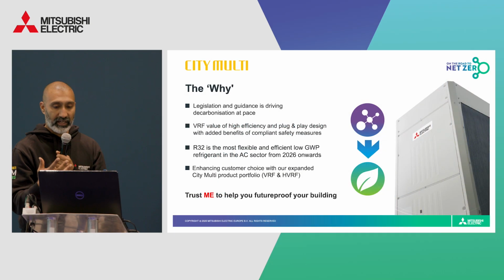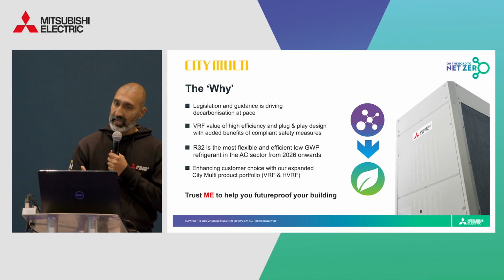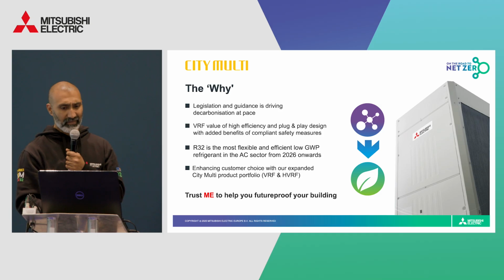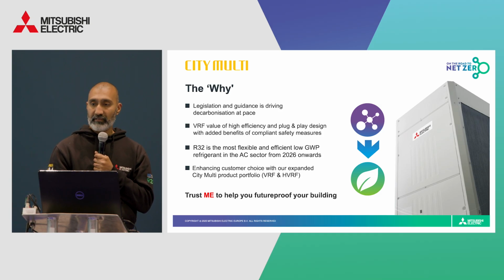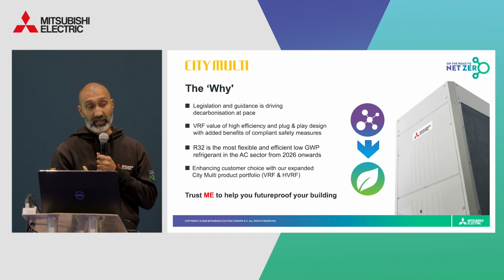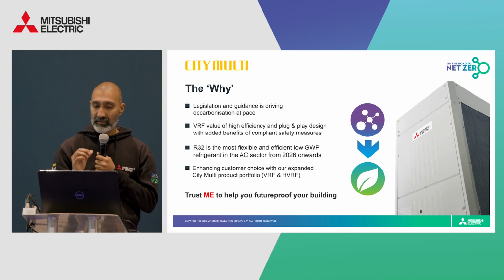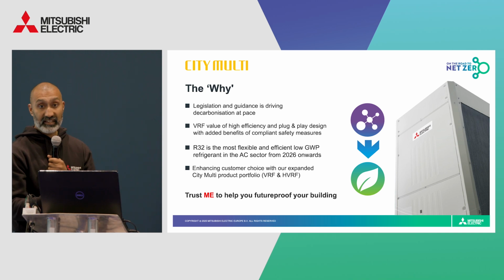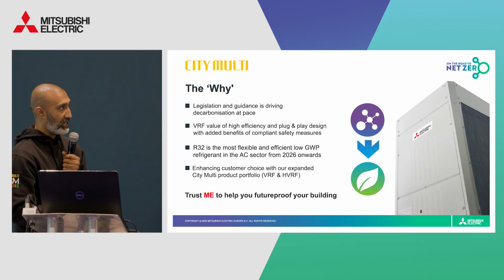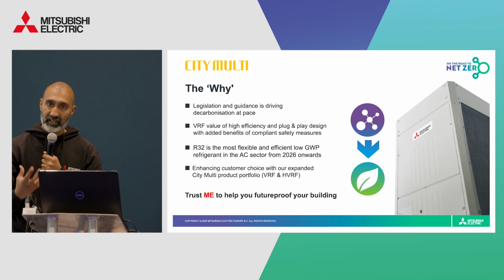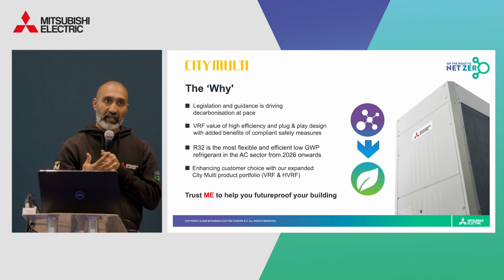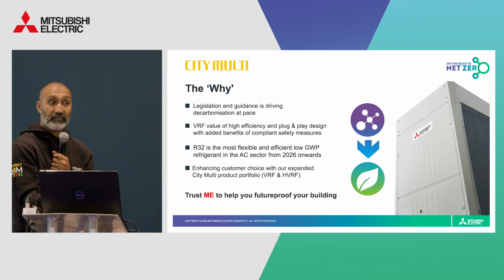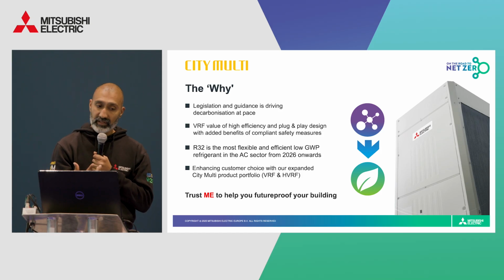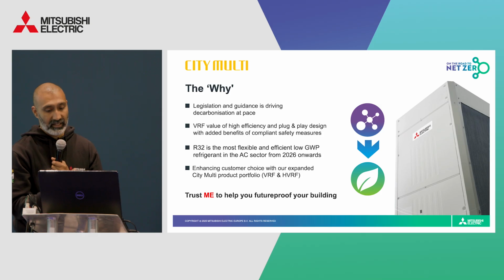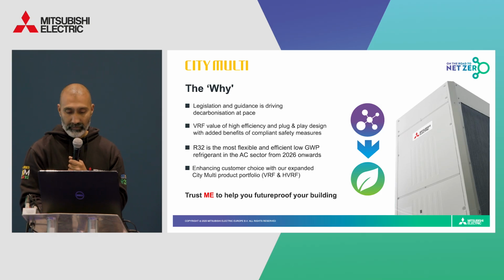Now, we mentioned this already a few times. The EU F-gas regulations will significantly impact the type of refrigerants that we can use in VRF systems. And by 2029, new R410A VRF systems will no longer be allowed on the market due to their high GWPs. However, it is important to note that R410A is still acceptable for use in VRF systems for the time being. But the industry has been moving for some time actually. So R32 has really been adopted in the industry and is now almost seen as the go-to refrigerant. But it's classified as A2L, mildly flammable, so we need to include safety features like leak detectors, alarms, and safety shutoff valves in any new product development.